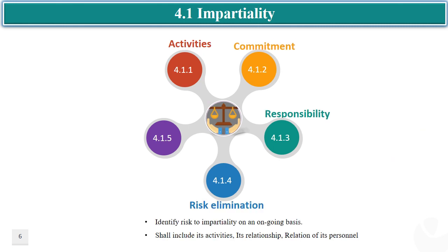As per sub-clause 4.1.4, the laboratory shall proactively identify all potential risks to impartiality on a regular basis. These risks may arise internally from laboratory activities or laboratory personnel, or may arise externally from interested parties or the context in which the laboratory operates. The presence and nature of risks may vary from laboratory to laboratory depending on its operational context. A few examples are: one, business relationships between the laboratory and the client; two, family or personal relationships between people in the laboratory involved in laboratory activities and the client.